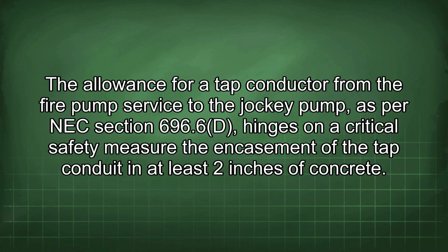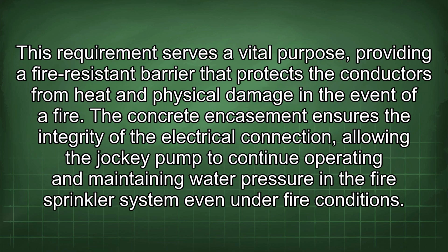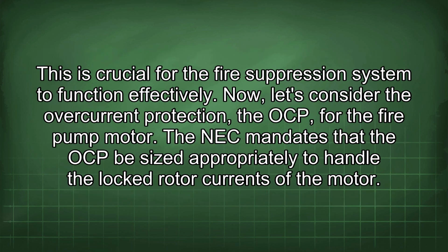The allowance for a tap conductor from the fire pump service to the jockey pump, as per NEC section 696.6d, hinges on a critical safety measure: the encasement of the tap conduit in at least 2 inches of concrete. This requirement serves a vital purpose, providing a fire-resistant barrier that protects the conductors from heat and physical damage in the event of a fire. The concrete encasement ensures the integrity of the electrical connection, allowing the jockey pump to continue operating and maintaining water pressure in the fire sprinkler system even under fire conditions. This is crucial for the fire suppression system to function effectively.